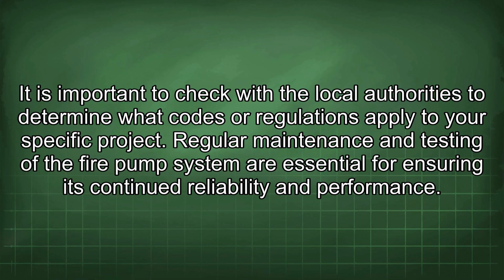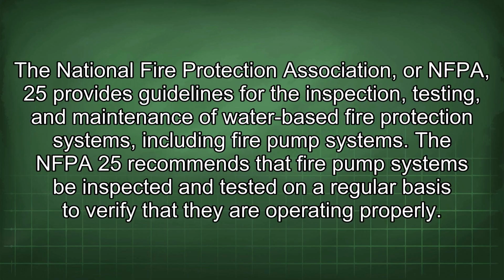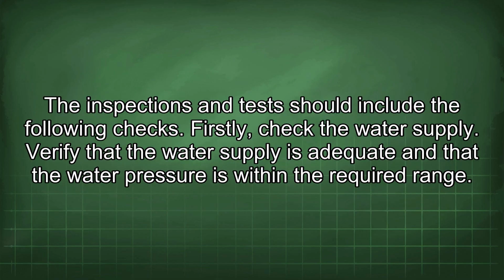Regular maintenance and testing of the fire pump system are essential for ensuring its continued reliability and performance. The National Fire Protection Association, or NFPA 25, provides guidelines for the inspection, testing, and maintenance of water-based fire protection systems, including fire pump systems. The NFPA 25 recommends that fire pump systems be inspected and tested on a regular basis to verify that they are operating properly. The inspections and tests should include the following checks.